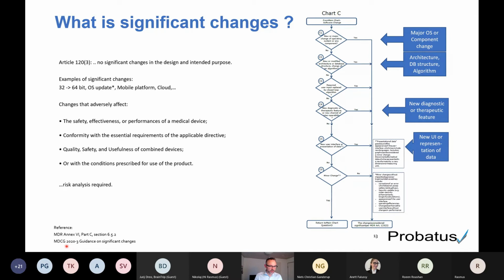There is in this guidance document, MDCG 2020-3, this flowchart, and I'm sorry it's too small here to read it, but it states that in the first one, if there's a major change to the OS or any other component of the software, then it is considered a significant change. If there are changes to the architecture of the software, database structure, or to an algorithm within the software, then it is considered a significant change. If it's adding new diagnostic and therapeutic features, it's a significant change. A new UI or representation of data is also considered a significant change. So only if we move a control or a button on the screen to another location within the same screen, it can be regarded as non-significant. And also some security patches are considered non-significant changes.